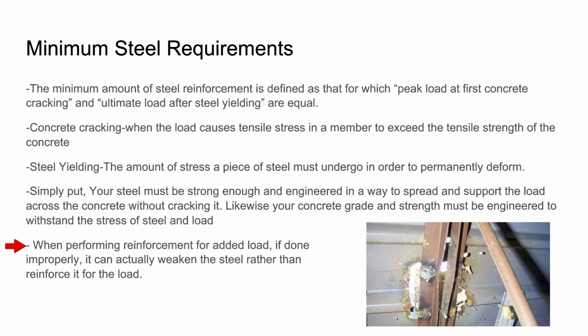When you are performing reinforcement for an added load, typically if it's within a couple hundred pounds or so, it doesn't make much difference. But if you're putting an RTU where there wasn't one before, a 7,000 pound system where there was a 5,000 pound system, or adding a curb adapter, that usually offsets the weight enough that added steel is needed for the building, then you really need to address those issues. Otherwise, you're going to run into further issues down the road.